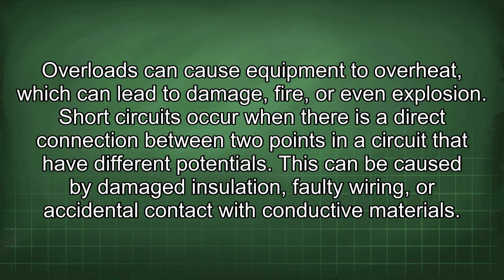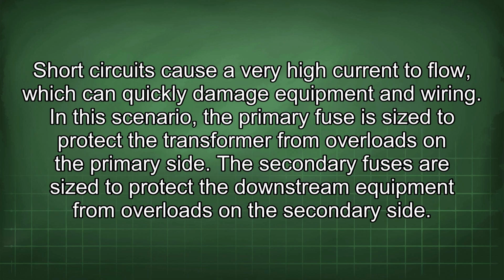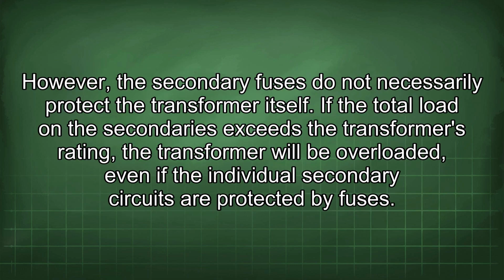Short circuits occur when there is a direct connection between two points in a circuit that have different potentials. This can be caused by damaged insulation, faulty wiring, or accidental contact with conductive materials. Short circuits cause a very high current to flow, which can quickly damage equipment and wiring. In this scenario, the primary fuse is sized to protect the transformer from overloads on the primary side. The secondary fuses are sized to protect the downstream equipment from overloads on the secondary side. However, the secondary fuses do not necessarily protect the transformer itself. If the total load in the secondaries exceeds the transformer's rating, the transformer will be overloaded, even if the individual secondary circuits are protected by fuses.